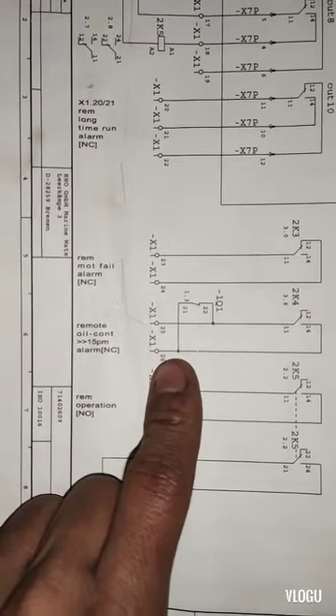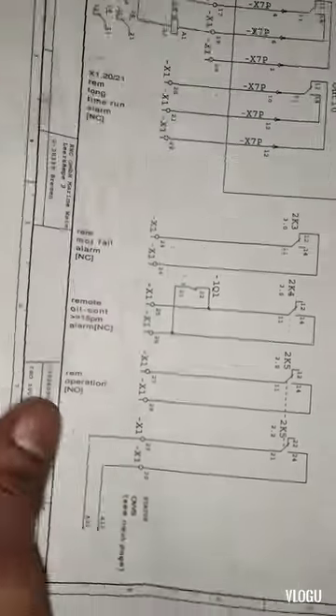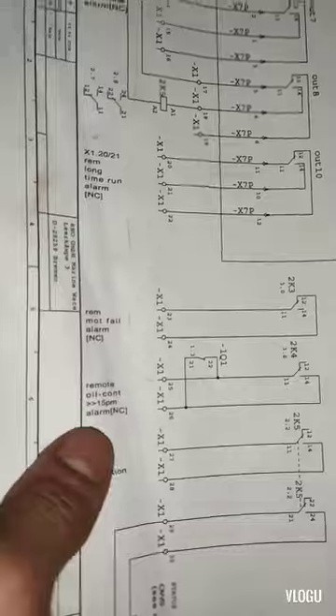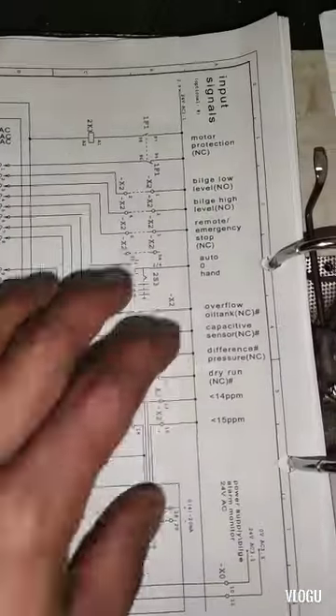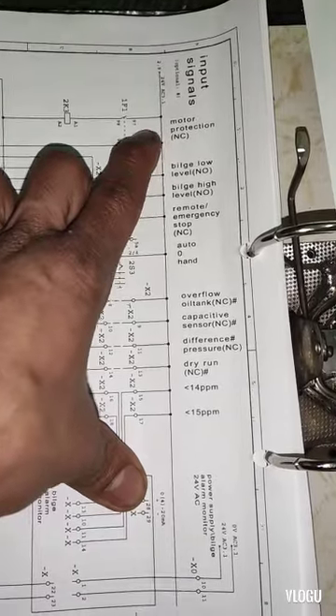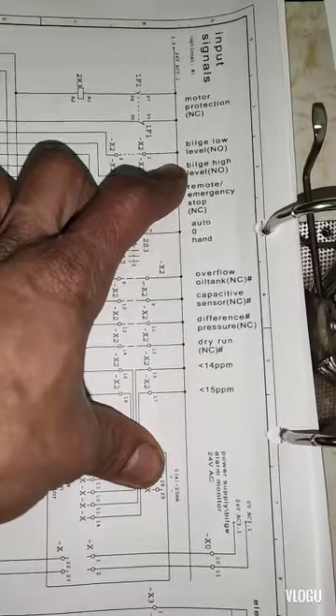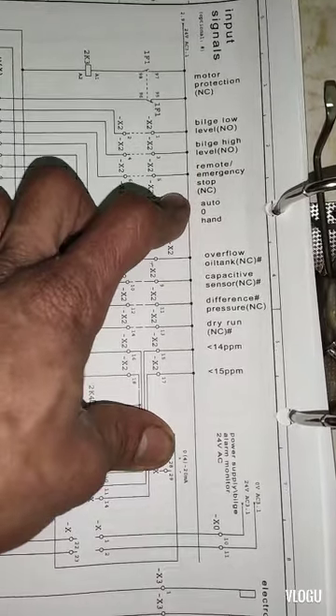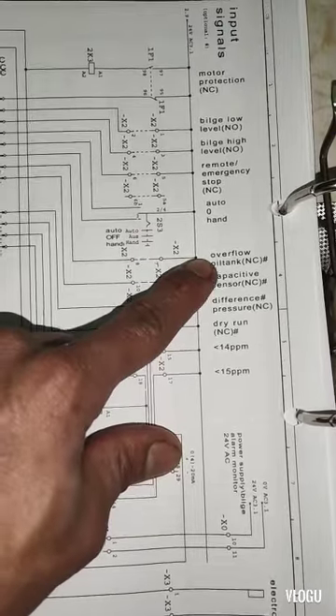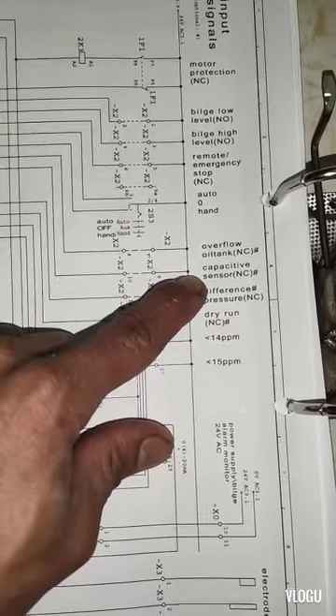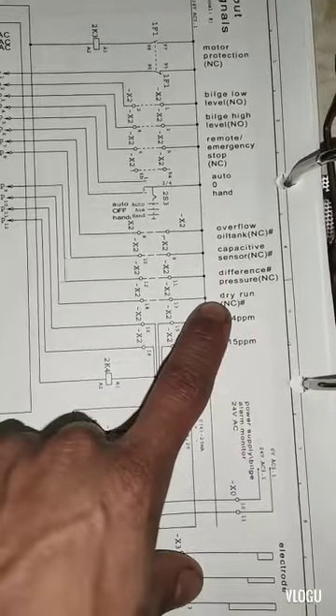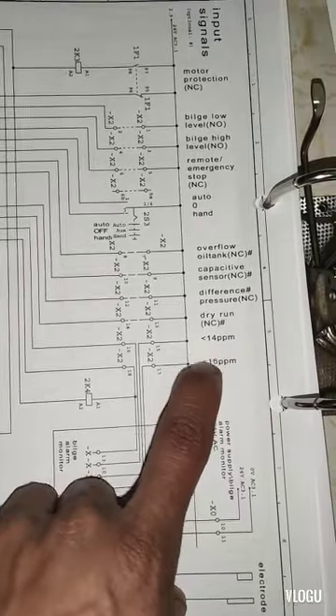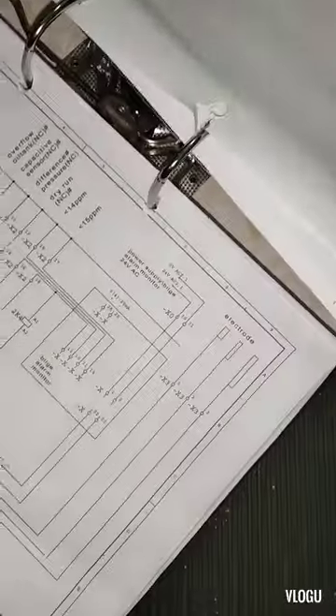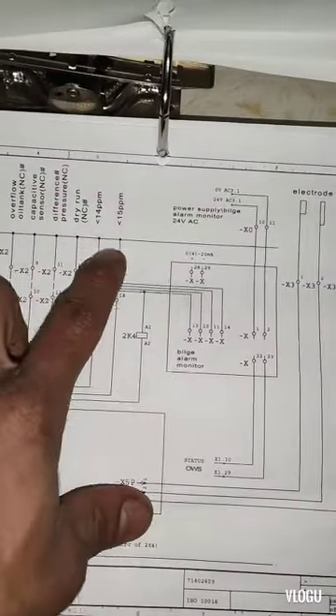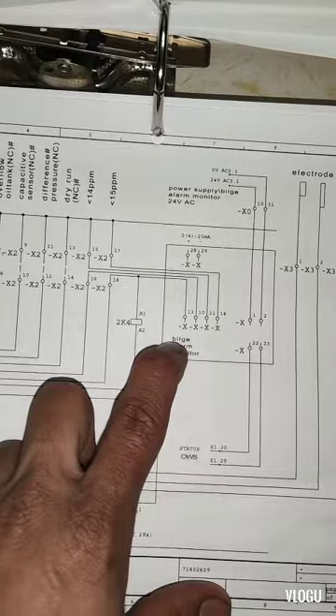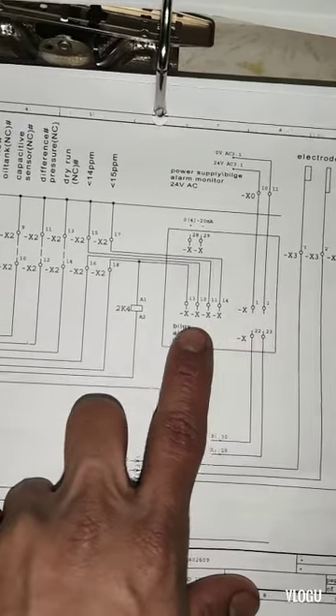1Q1, I think this is the main switch. If you switch off the system, they give an alarm, but it's not the alarm that we need. Motor protection, bilge low level, normally open. Bilge level high, normally open. Overflow, capacitive sensor, differential pressure, dry run, and here we have the 14 ppm signal and 15 ppm, going to the bilge alarm monitor.